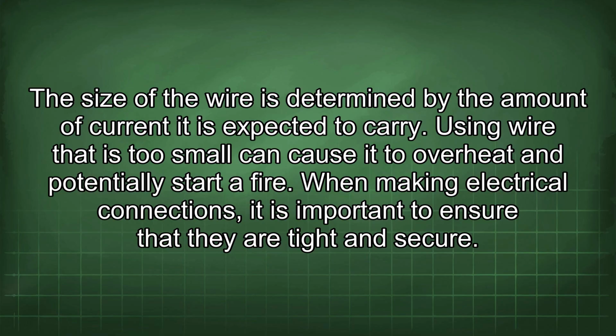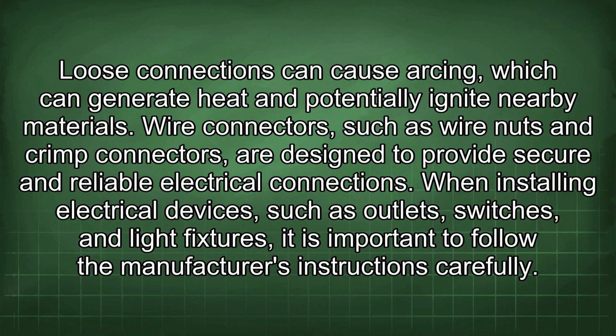When making electrical connections, it is important to ensure that they are tight and secure. Loose connections can cause arcing, which can generate heat and potentially ignite nearby materials. Wire connectors, such as wire nuts and crimp connectors, are designed to provide secure and reliable electrical connections.